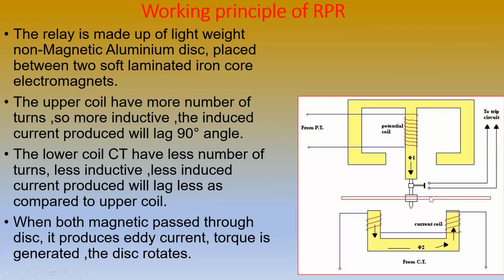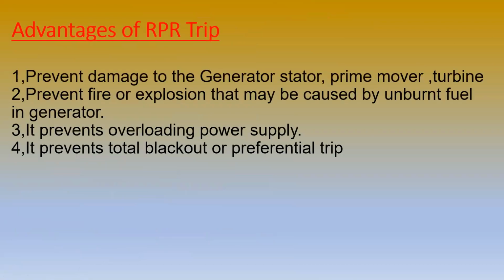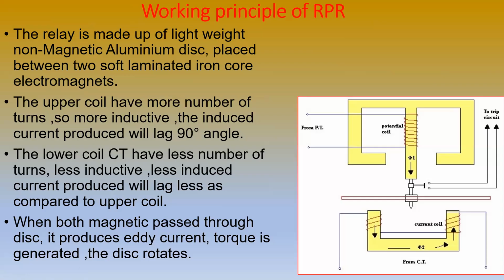So that is normal rotation. When reverse power acts, that is, when the reverse current is formed in the PT coil and the CT coil, that is, the potential transformer and the current transformer, what will happen in that condition? The disc starts to rotate in the anti-clockwise direction. The stopper will now move, and it gets towards the trip circuit, and the circuit is tripped. So this is the working principle of the reverse power relay trip.